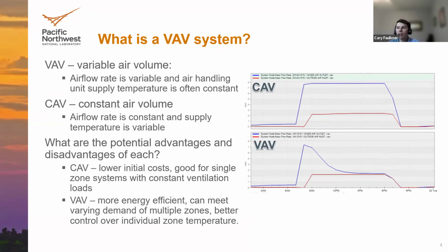Whereas VAVs are going to be more commonly used for larger buildings, especially larger commercial buildings. They can be more energy efficient because you have this aspect of being able to change the airflow rate and potentially avoid overcooling or overheating, as well as just maybe a better, more optimal way to provide air into the building by modulating the airflow rate. As well as, for multi-zone buildings, you can meet varying demands of those zones better, and perhaps have better control over individual zone temperature through that airflow modulation.